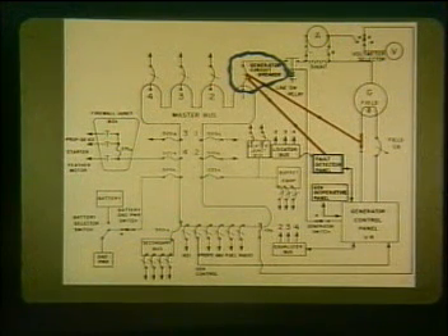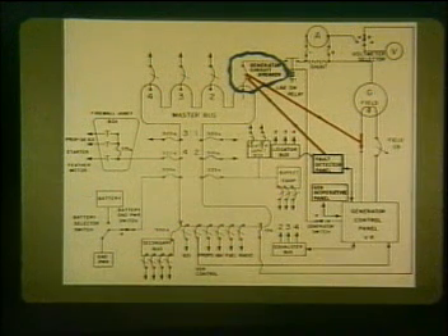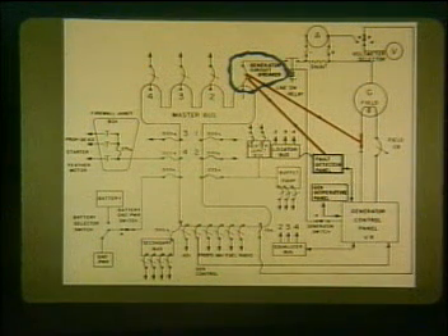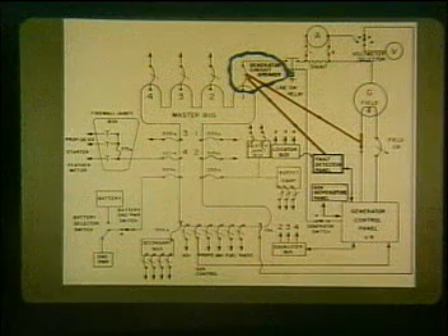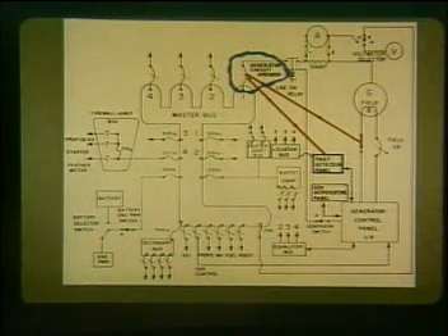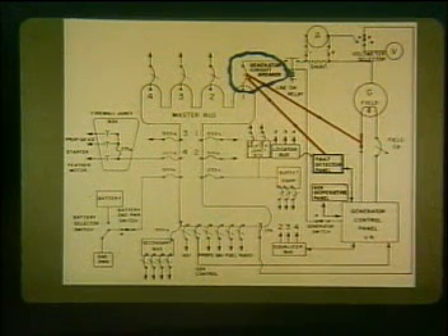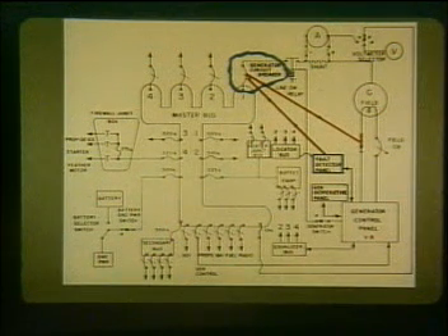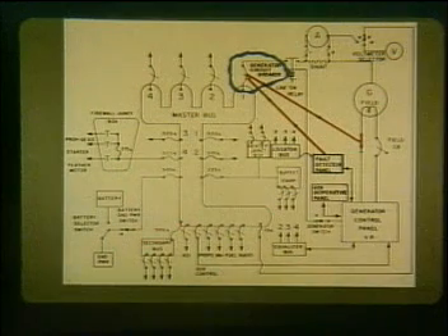In the Group 2 aircraft, a generator circuit breaker replaces the reverse current circuit breaker and the overvoltage protector. The generator circuit breaker provides the following protection. 1. Reverse current in excess of 300 amps. 2. Short to the generator supply line. 3. Excessive generator voltage. And 4. A generator overload. This overload protection does not exist in the earlier system.